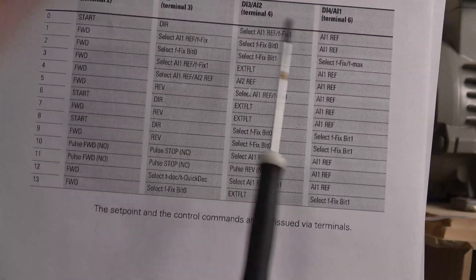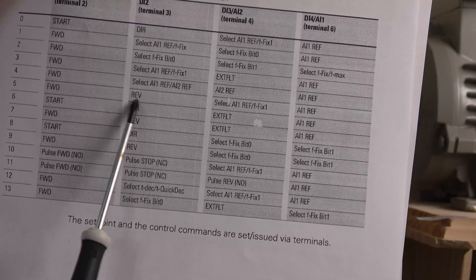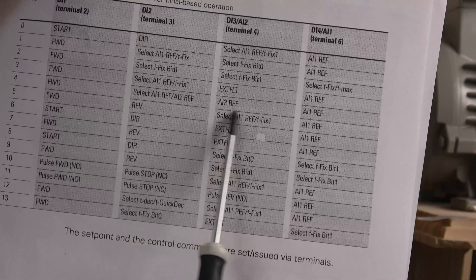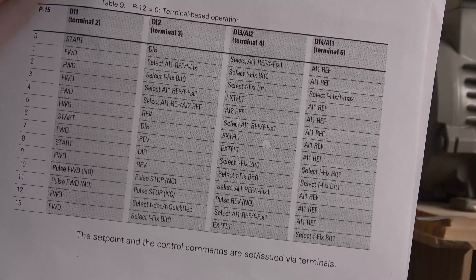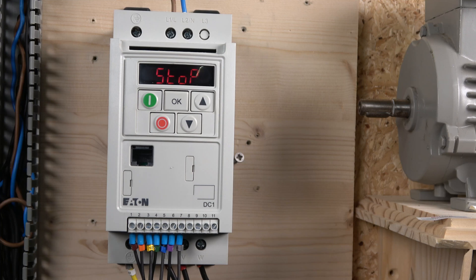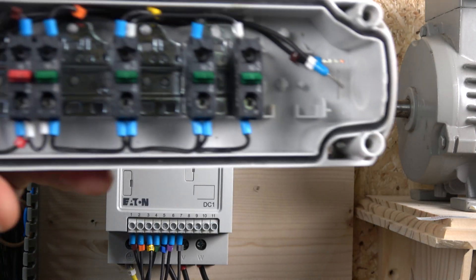Whichever station you want to build, you have all sorts of selections. I want to run this with forward activated on digital input one, reverse activated on digital input two, and a jog button — which in the manual is called fixed speed one rather than jog. You can set that as a jog and its frequency will be read from whatever is preset in the speed one parameter. Then we have an AI1 reference on terminals 5, 6, and 7. For this station, I've chosen parameter 15 set to five.